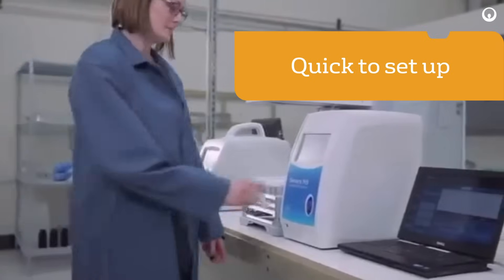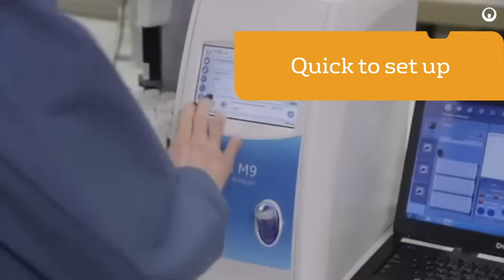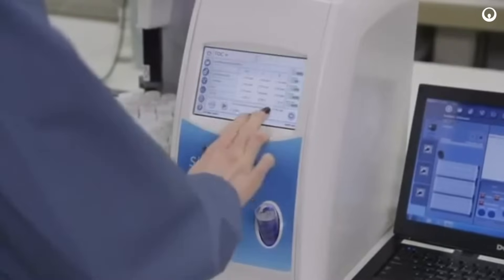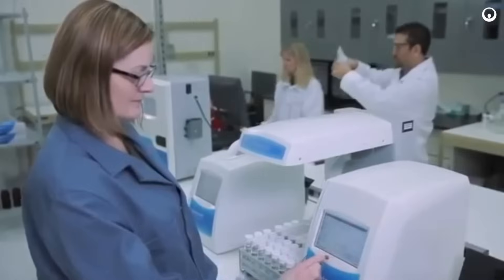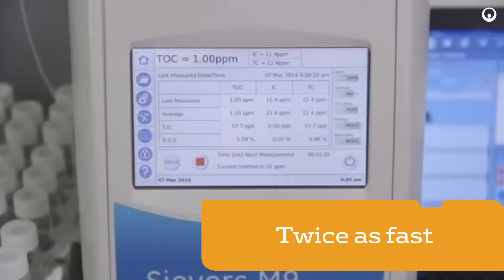Still quick to set up, easy to use, and maintain, the new M-Series is faster, smarter, and more versatile than legacy Sievers TOC analyzers. M-Series analyzers are twice as fast as the previous generation's Sievers 900 technology, providing results in only two minutes.